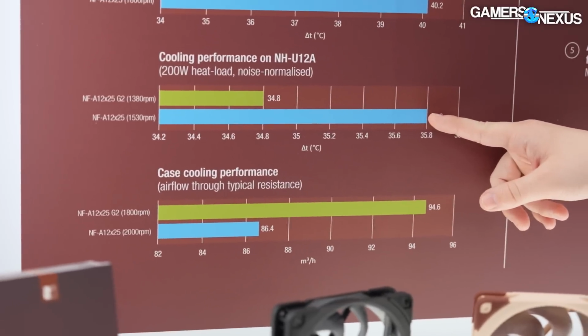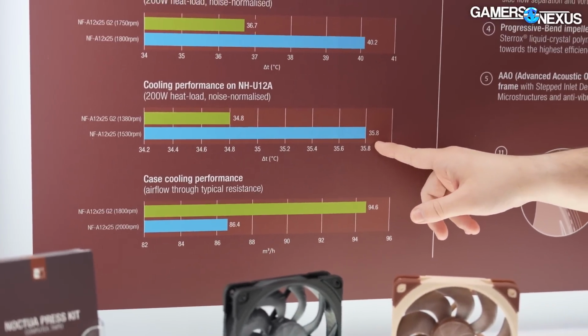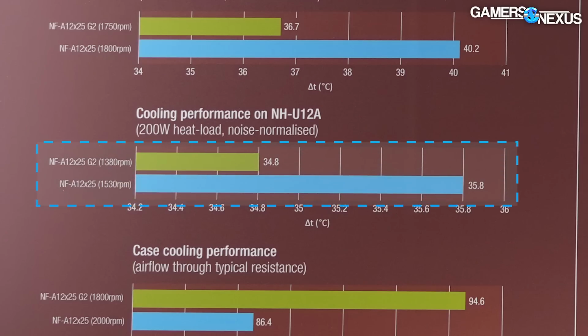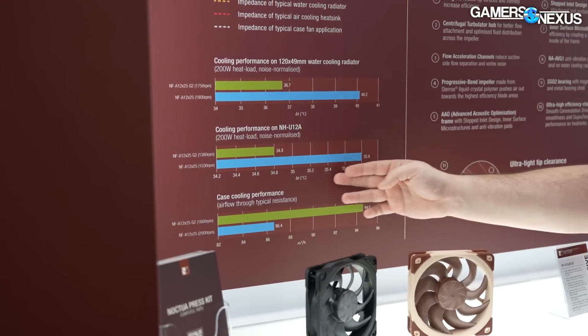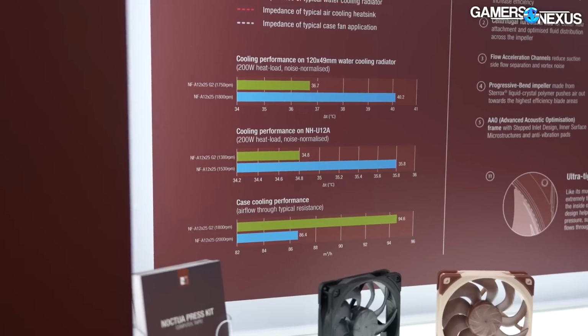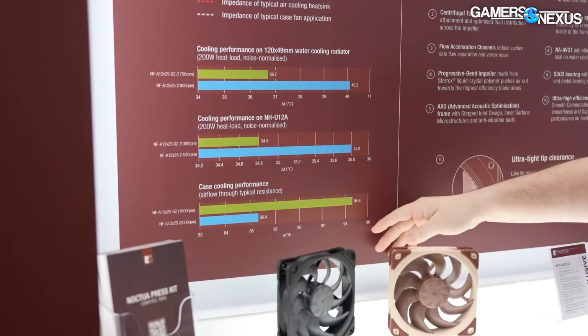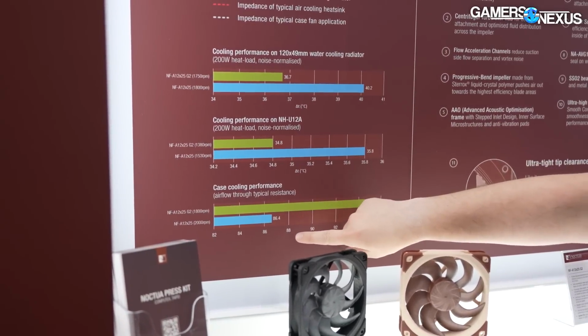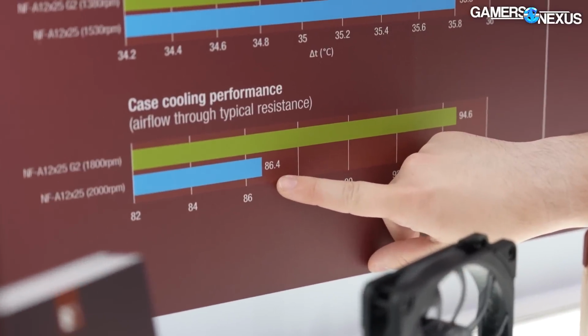The air cooler here, so this is call it a 1 degree difference between the 200 watt heat load noise normalized on the U12A, and I just want to point out that the scale of 36 to 34.2, this is what NVIDIA's doing to this industry. This is an NVIDIA chart scale is what this is. But anyway, 1 degree, to be fair, on an air cooler is a lot. That's kind of the difference we tend to see top to bottom on some of the same price ones.